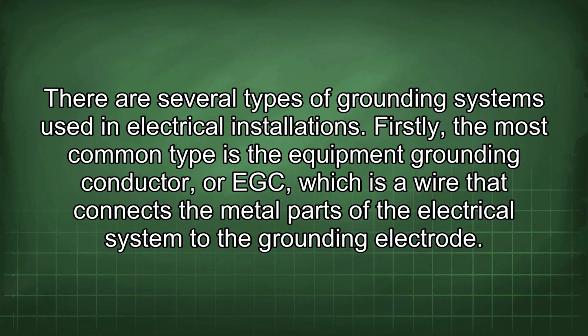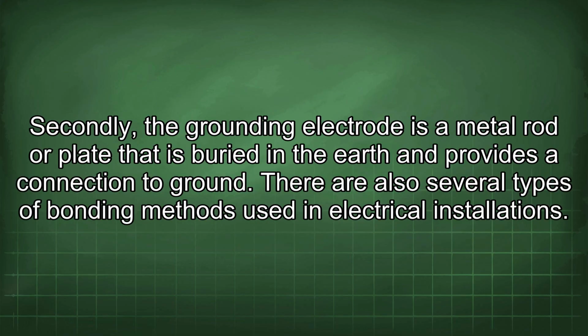There are several types of grounding systems used in electrical installations. Firstly, the most common type is the equipment grounding conductor, or EGC, which is a wire that connects the metal parts of the electrical system to the grounding electrode. Secondly, the grounding electrode is a metal rod or plate that is buried in the earth and provides a connection to ground.